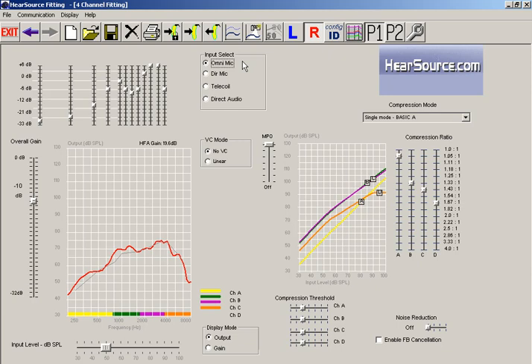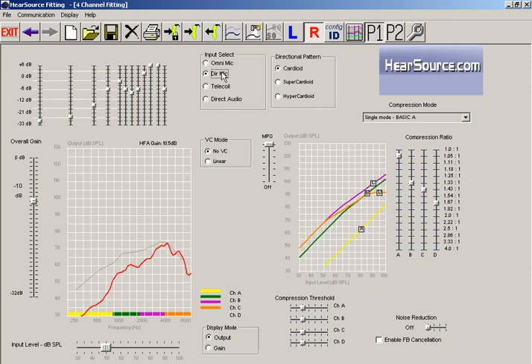Now in those environments that you need a little bit of filtration where you're trying to eliminate some background noise, you're probably going to want to use a directional microphone system. Now there are a few limitations with the directional microphone system, such as if a hearing aid is too small, adding a second microphone to the system takes up too much space. But a directional microphone system does allow us to filter out some of that background noise.